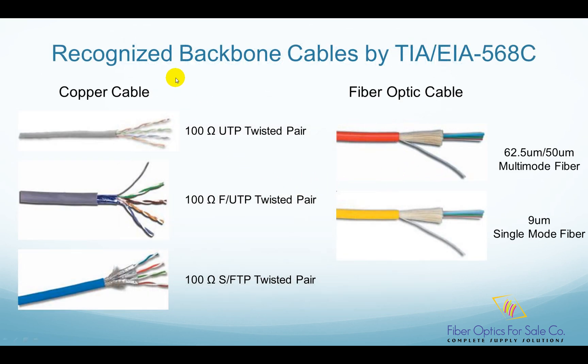The TIA/EIA 568C recognizes several types of cables as backbone cables. On the copper cable side, it recognizes 100 ohm twisted pair copper cable, which includes 100 ohm unshielded twisted pair UTP cable, 100 ohm screened foiled UTP cable, and 100 ohm screened shielded twisted pair SFTP. On the fiber optic cable side, it recognizes 62.5 micron or 50 micron core multimode fiber and 9 micron single-mode fiber.